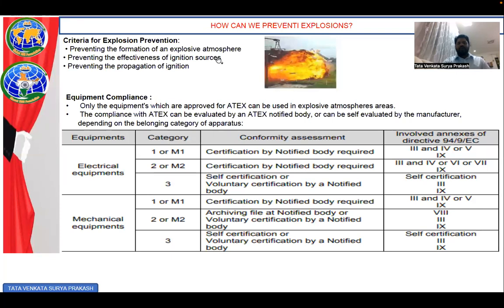So now, how can we prevent explosions? This we wanted to know, because the ATEX regulations and all are there to avoid creation of an explosive environment. So the criteria of explosion prevention is basically, as the primary step, preventing the formation of an explosive atmosphere. If you prevent the formation of the explosive atmosphere itself, that means you are eliminating the hazard itself. The second is preventing the effectiveness of ignition sources. Even if the explosive atmosphere is formed, if you don't supply an ignition source within the vicinity of the zone, then you are avoiding the explosion.